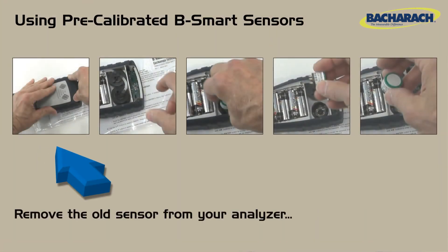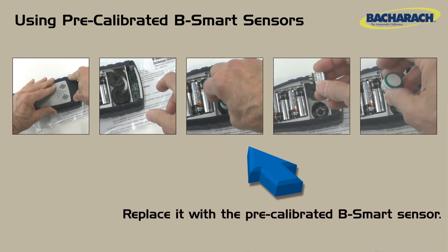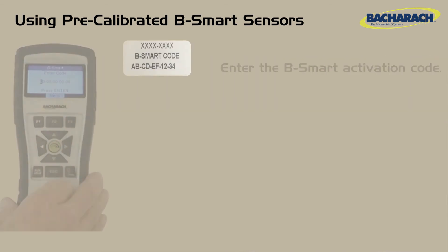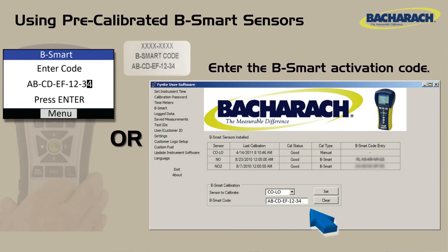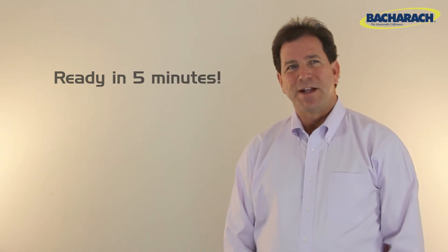Start by removing the old sensor from your analyzer. Next, replace it with a pre-calibrated B-Smart sensor. Enter the B-Smart activation code either directly into your analyzer or through Bacharach's Fyrite user software. Repeat this process if you've ordered multiple sensors. Your analyzer is ready to go in under five minutes. To maintain your enrollment in the program, it's important that you return your used sensor to Bacharach in the prepaid envelope provided.